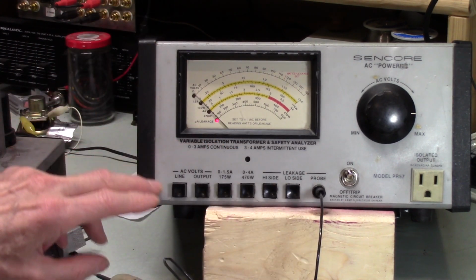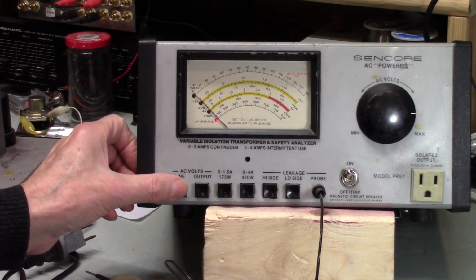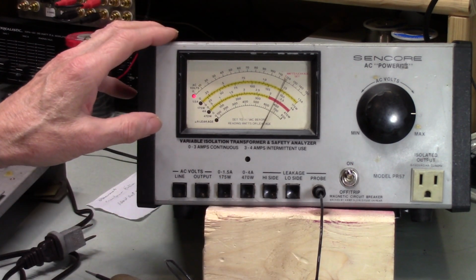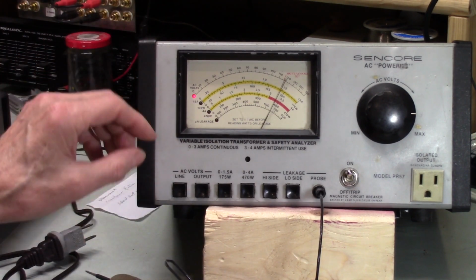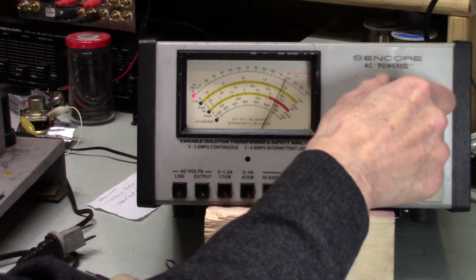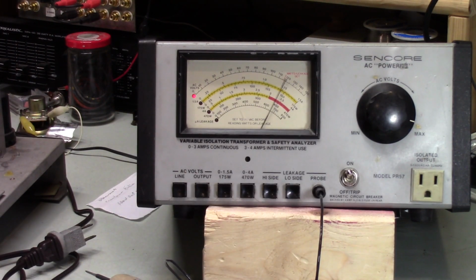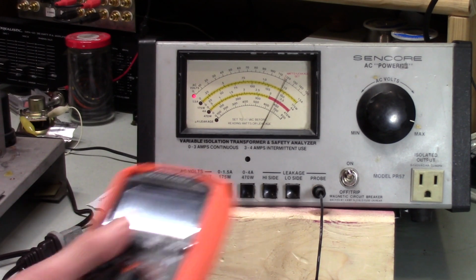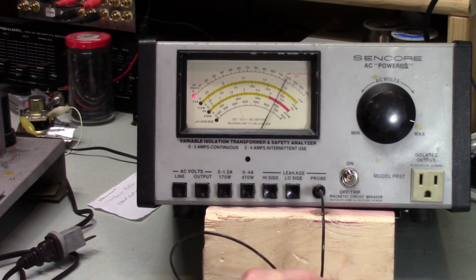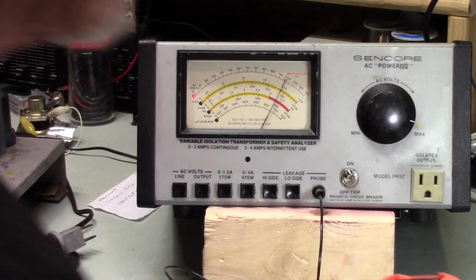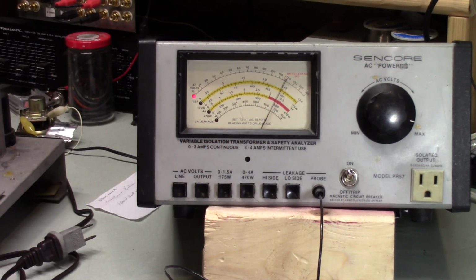Let's take a quick look at the buttons on this. The line button tells you what the line voltage is, and it's interesting, it's showing less than it usually does, yet I'm pretty sure my voltage here has not become less. That may mean this needs to be calibrated. I'm not going to worry about it right now, but it reads 121.3, and this is saying very close to 120, so it's about a volt off.